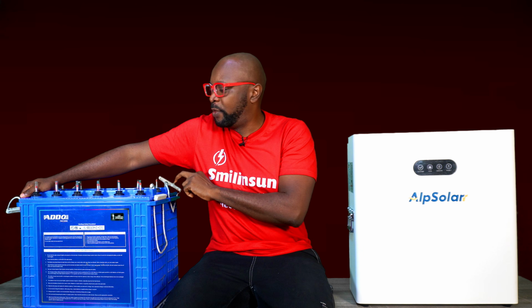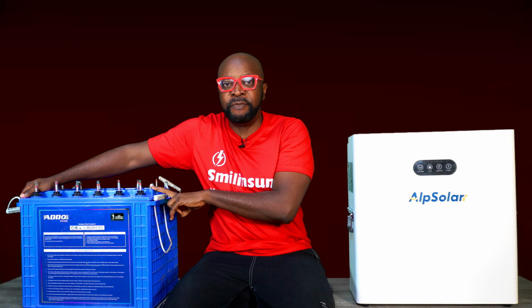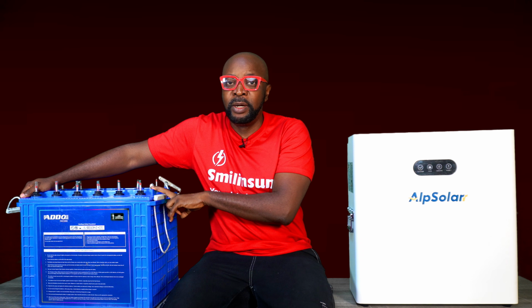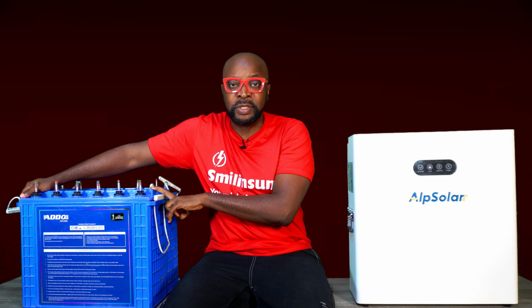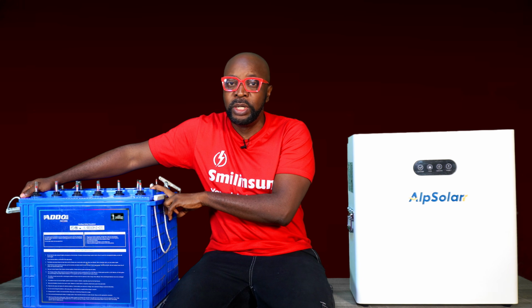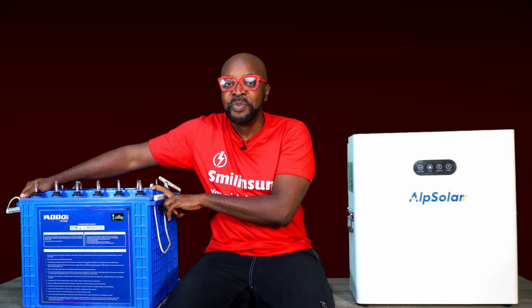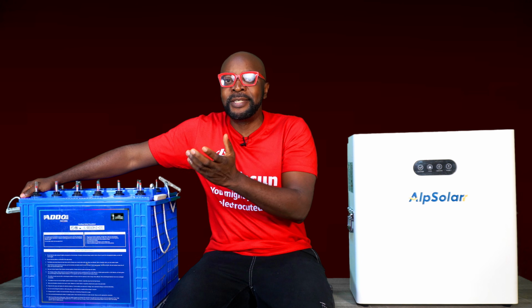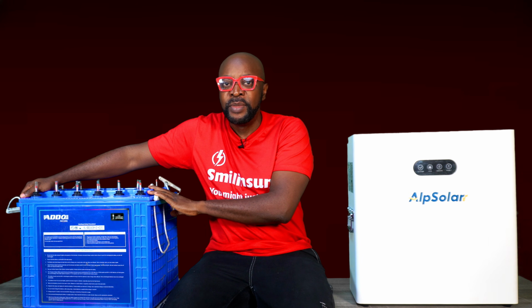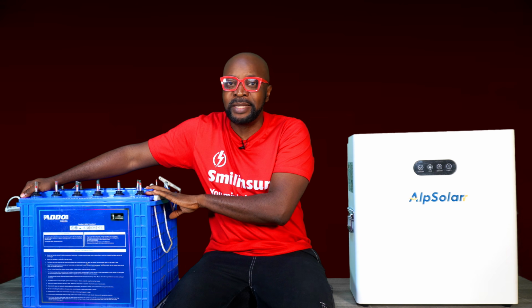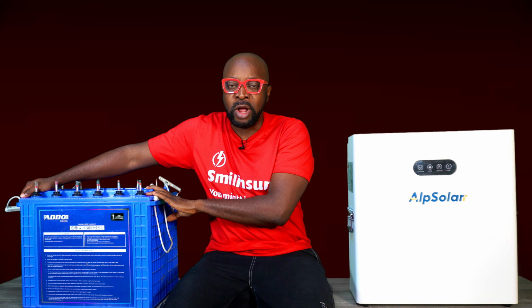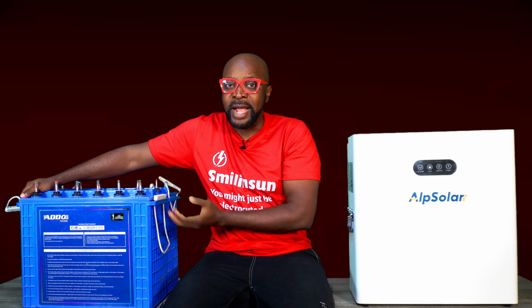So let's say the voltage of this battery is currently 51 volts. When you put a big load on this battery, it is going to drop to as much as 49 volts. It is called the voltage collapse. It happens to the flooded lead acid battery. Lead acid batteries in general, when they have a heavy load, which they see as a surge, the voltage will drop. But when you take off that load, it rises back.